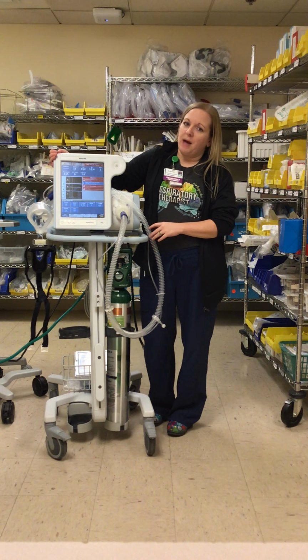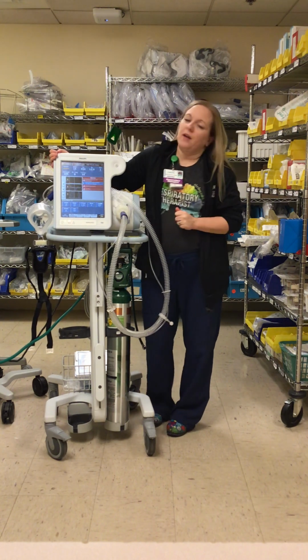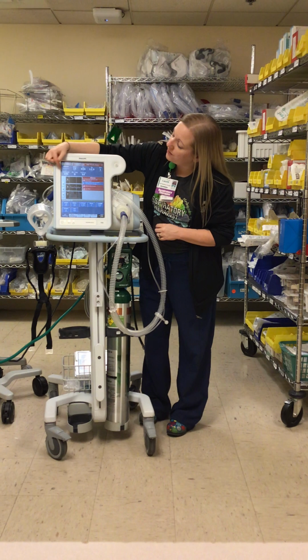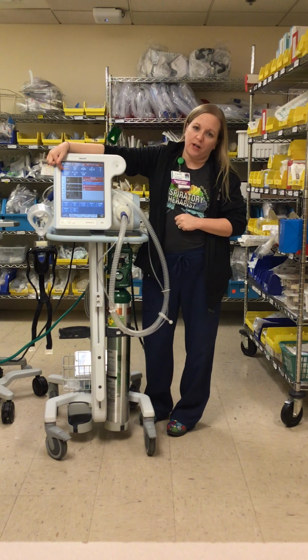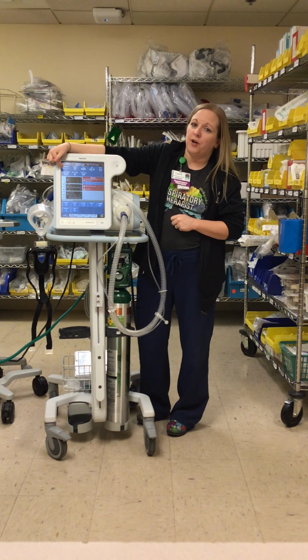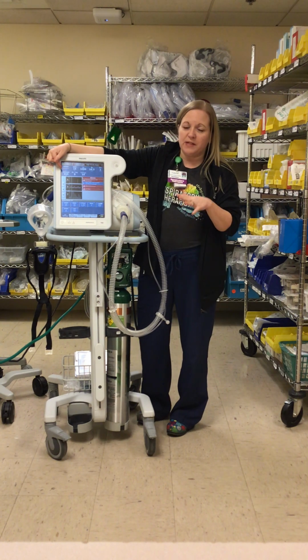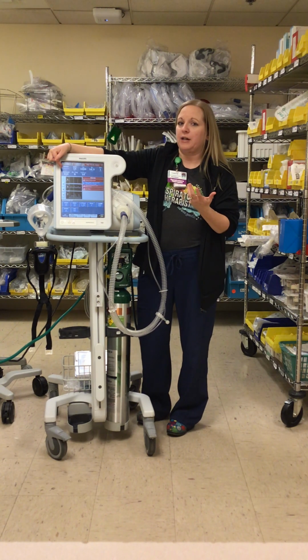So patients that are on BiPAP or CPAP have a leak on their mask. So that number is right here. It says total leak 109. We like to see that number under 100. You don't want it to be 0. If it's 0, the mask is too tight and you'll have skin breakdown.